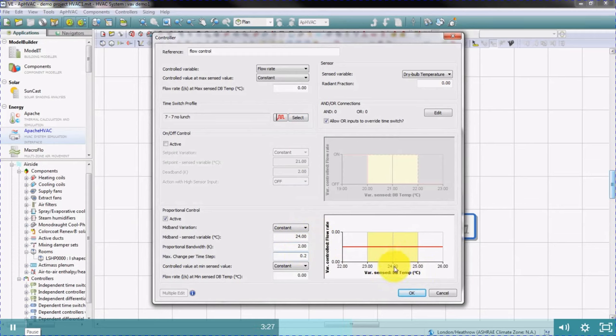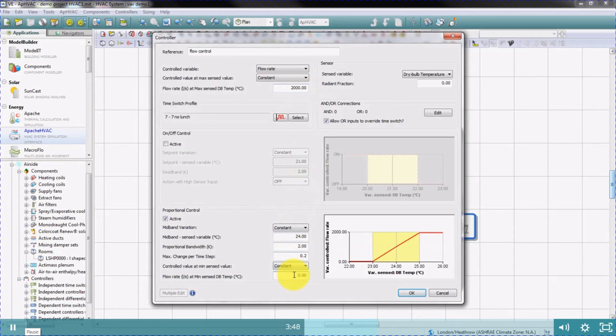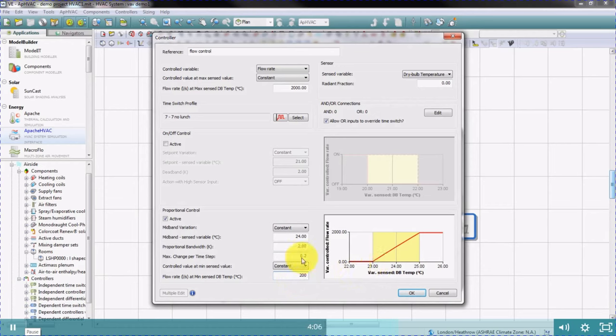You can see the graph updating. At the maximum sensed dry bulb temperature, which is at the top of the band — in this example 25 degrees — we'll enter the required flow rates. In this example it's a cooling system, so from our design calculations, we know we have a flow rate requirement of 2000 litres per second. At the bottom end of the band, we'll set the required flow rate when the room is at 23 degrees or below. In this example, we'll enter a flow rate of 200 litres per second. So the flow will vary between 200 and 2000 litres per second depending on the temperature in the zone.